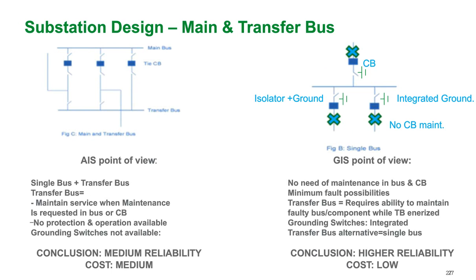So the next one is a main or transfer bus. Typically with a transfer bus, you have some auxiliary power, so you still have power during a maintenance cycle. So from an air insulated point of view, you increase your reliability here. You still have maintenance of your circuit breaker and bus. But with this, you have an increase in cost as well.